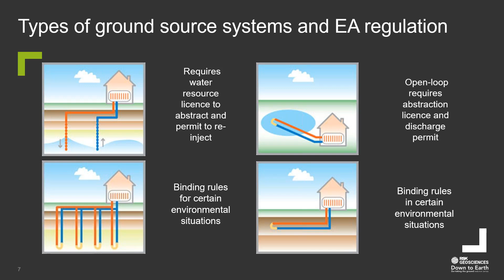Looking closer at an open loop scheme: here we have a series of rock lithologies with an aquifer at the bottom. Boreholes are drilled into it - a doublet in this case - taking what's called warm groundwater, though in the UK we're probably talking about 11 to 14 degrees. That water is taken up the borehole into the building, passed through the heat pump, and the cooler water, about 5-7 degrees cooler, is injected back into the aquifer at a suitable distance away, where it recharges by taking in solar heat from the sun.